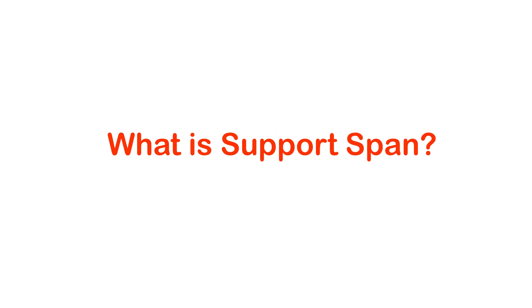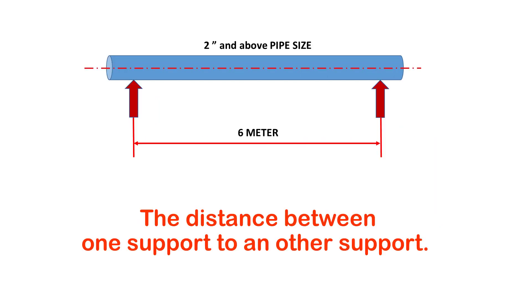Now let's understand what is support span. Support span is the distance between one support to another support. It is derived based on calculation for different sizes. Different sizes will have a different span length. Generally, two inch and above pipe sizes will have a span of six meters and above.